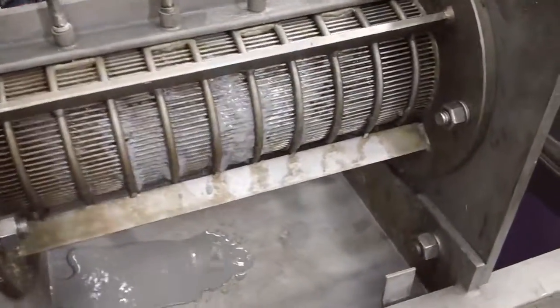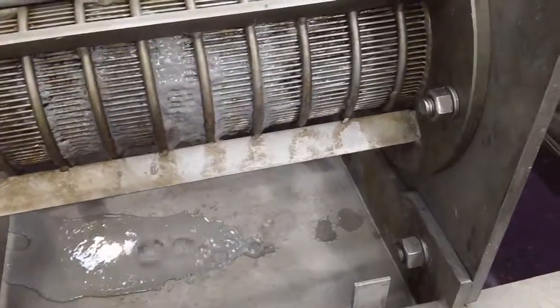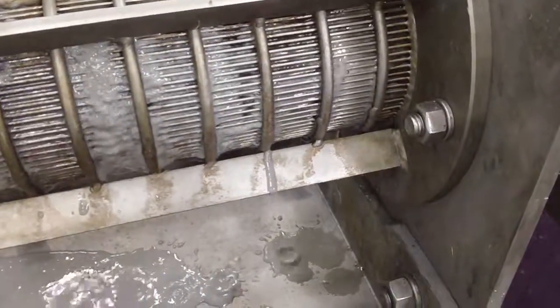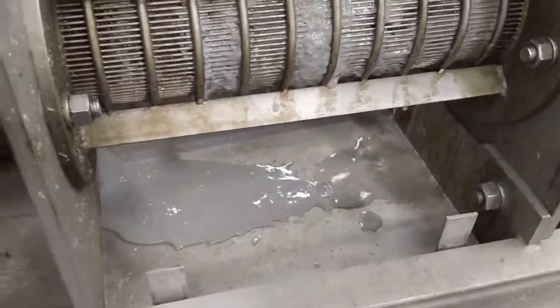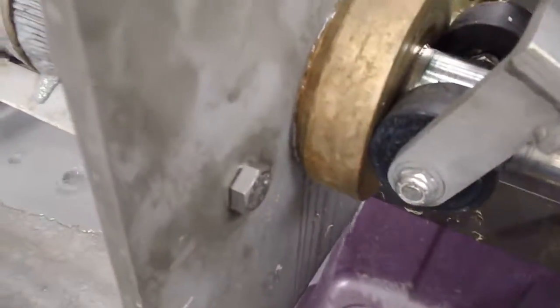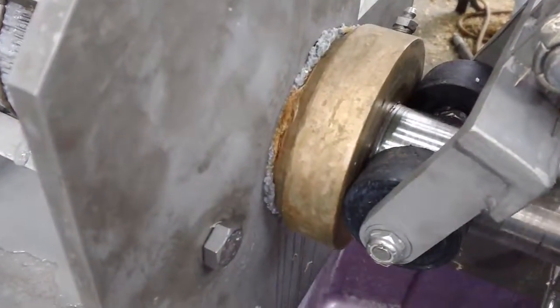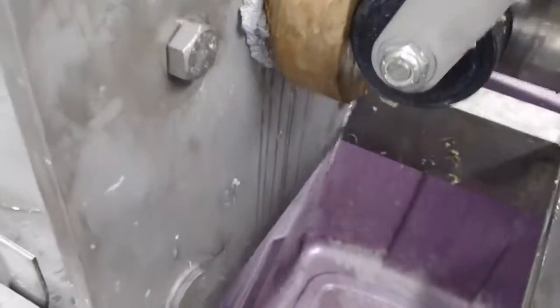You can tell we're filling the machine. It's starting to get some liquid out at the very discharge end. You will get leakage past the cone until you get a solids plug built there. What you're seeing leaking now was through the cone bushing, perhaps.